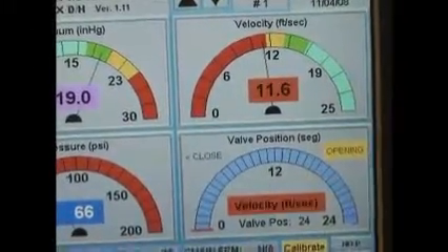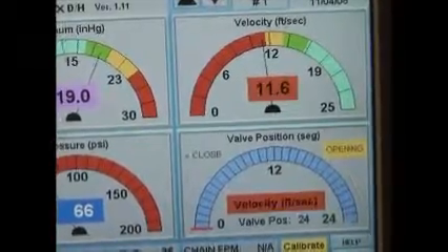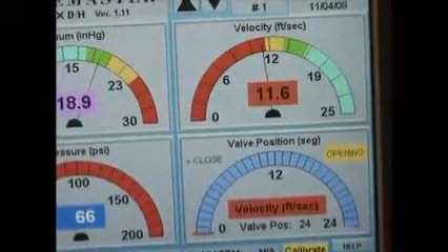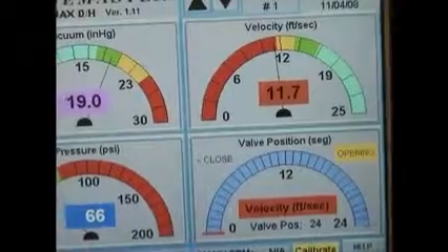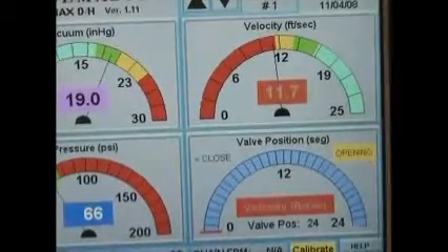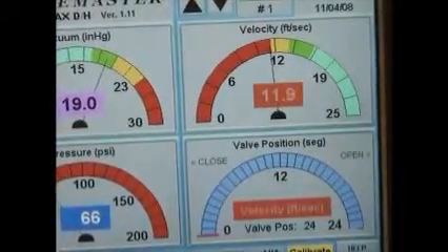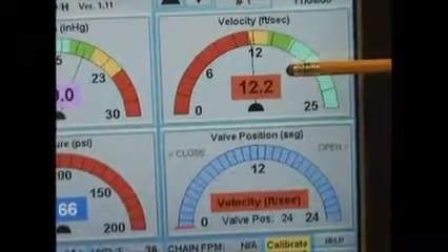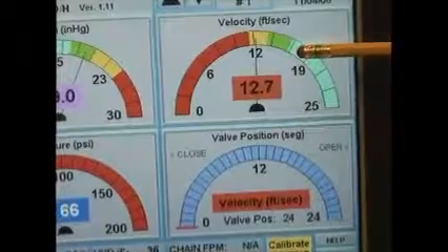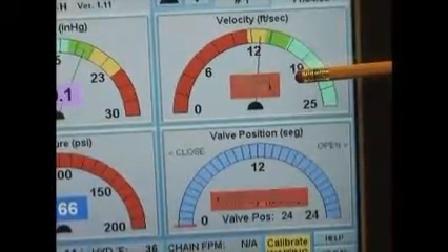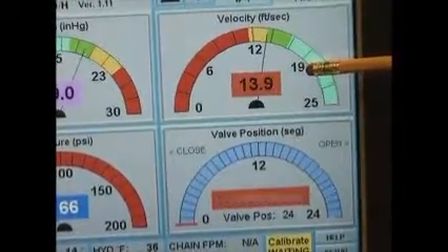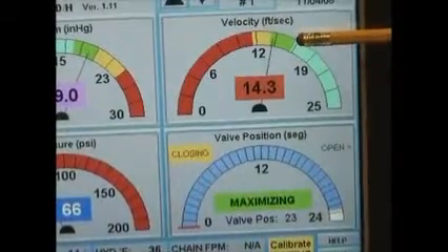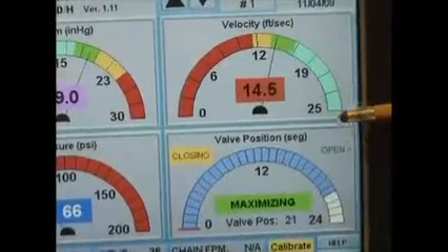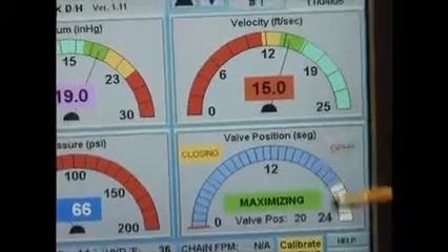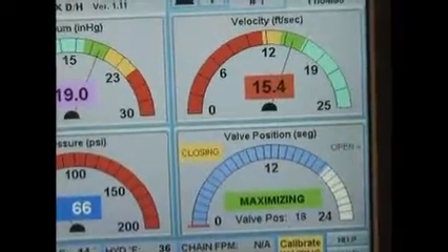So now we're letting as much fresh water as possible into the suction side of the pump, which in turn is reducing the percent solids in the pipeline. Once the percent solids in the pipeline starts to reduce, our velocity starts to pick itself back up again. As you can see, the velocity is starting to pick up higher and higher, and now it's back into the green zone. And once we're into the green zone, our valve can start closing itself up.